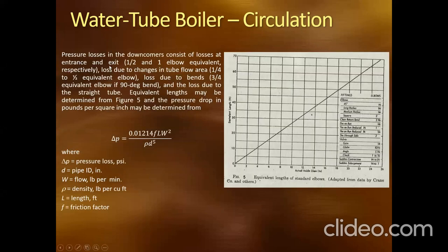Next, pressure loss in the downcomer consists of losses at entrance and exit, one-half velocity head and one elbow equivalent, sabi niya, respectively. Ito yung figure 5. Loss due to changes in tube area, which is 1/4 to 1/2 equivalent elbow. Loss due to bends, which is equal to 3/4 equivalent elbow if 90 degree bend. And the loss due to the straight tube.